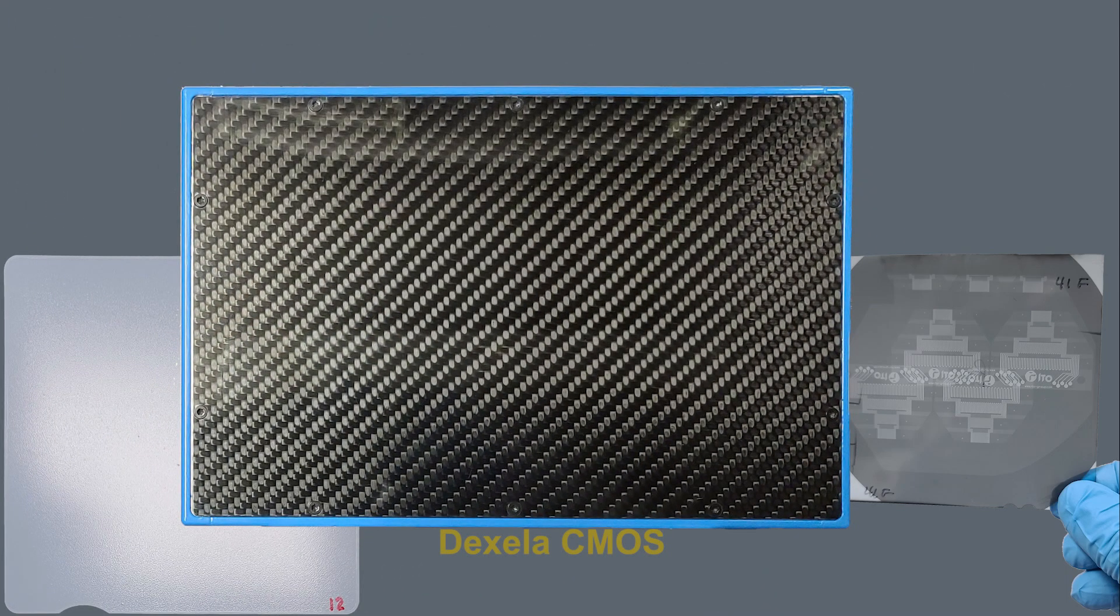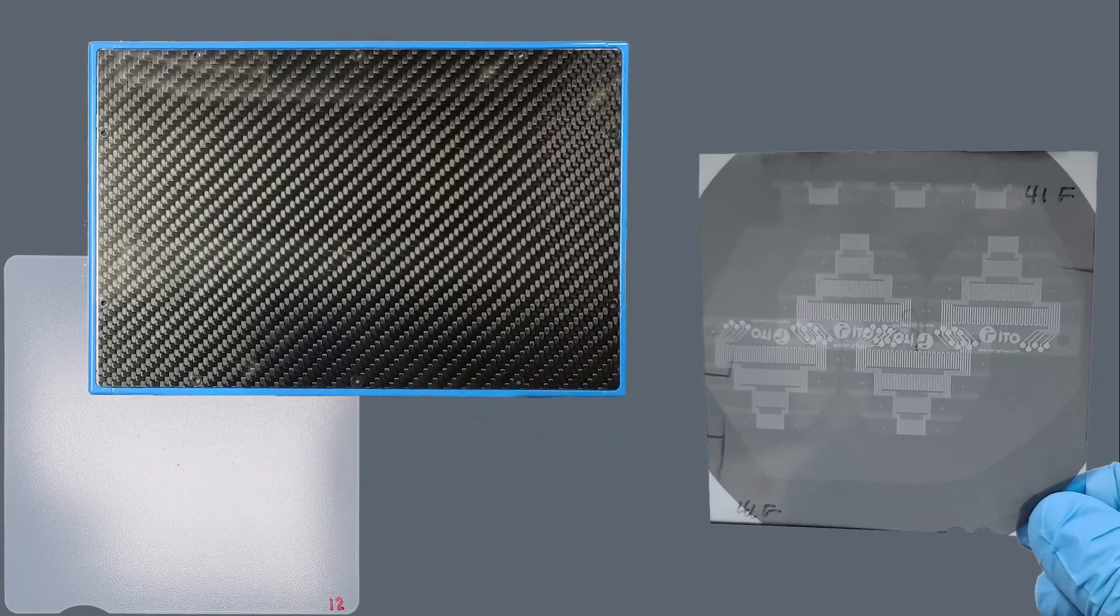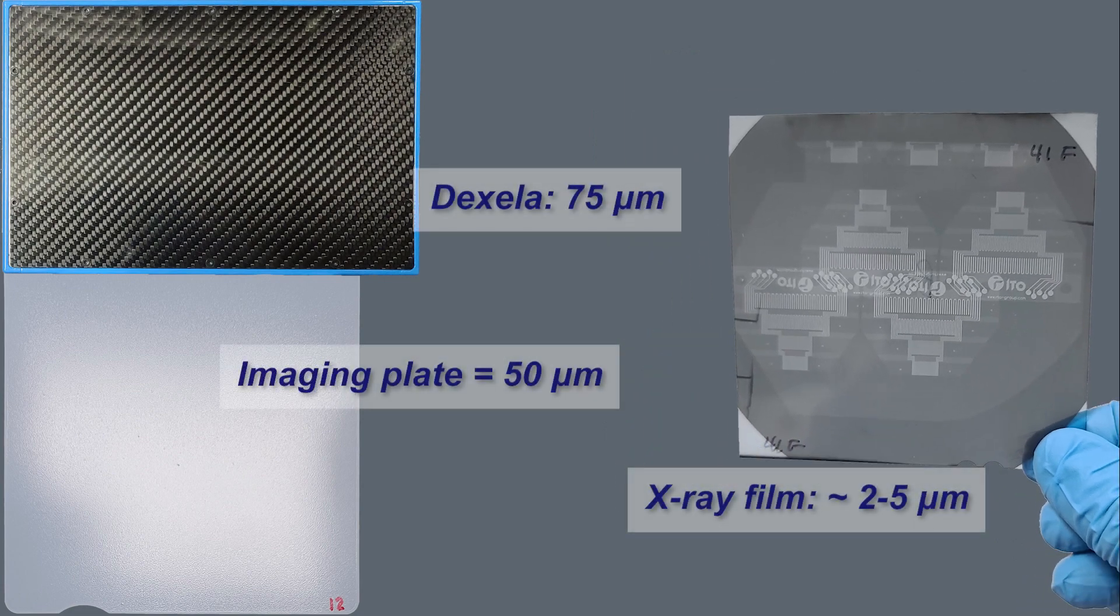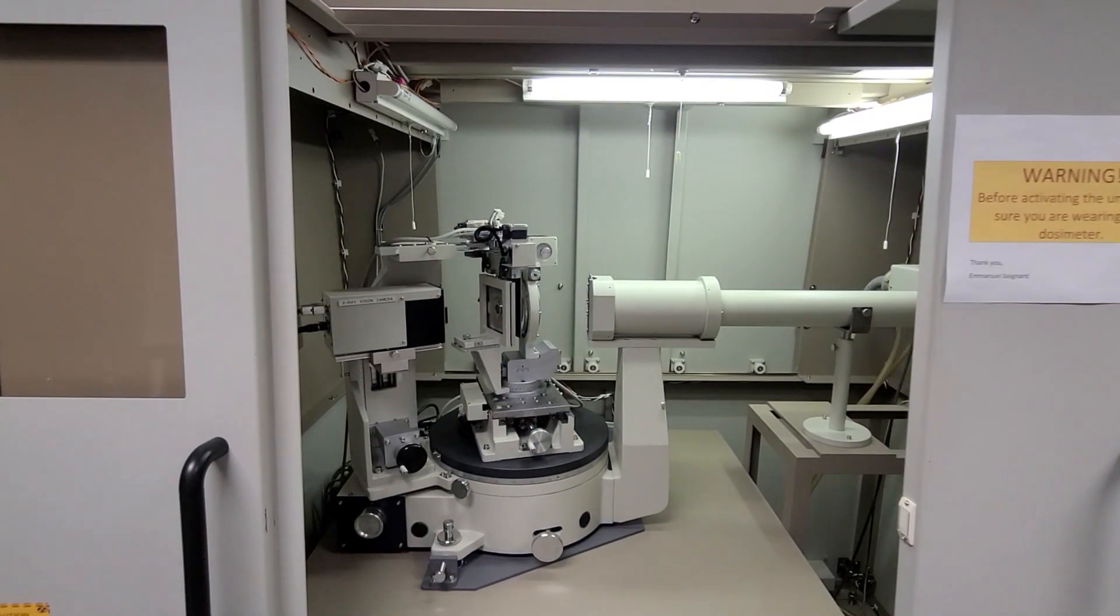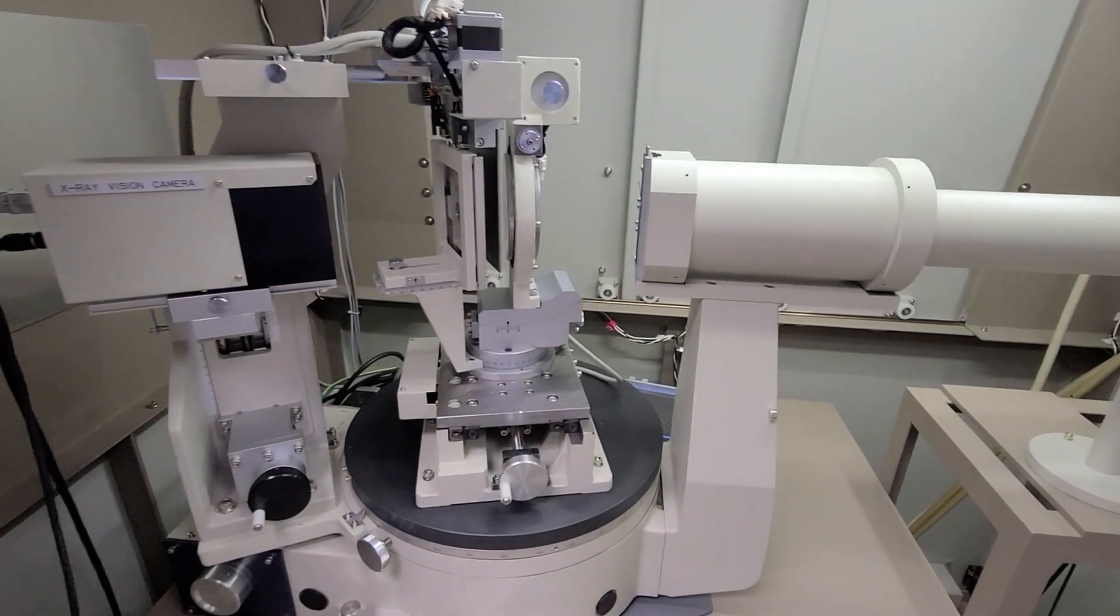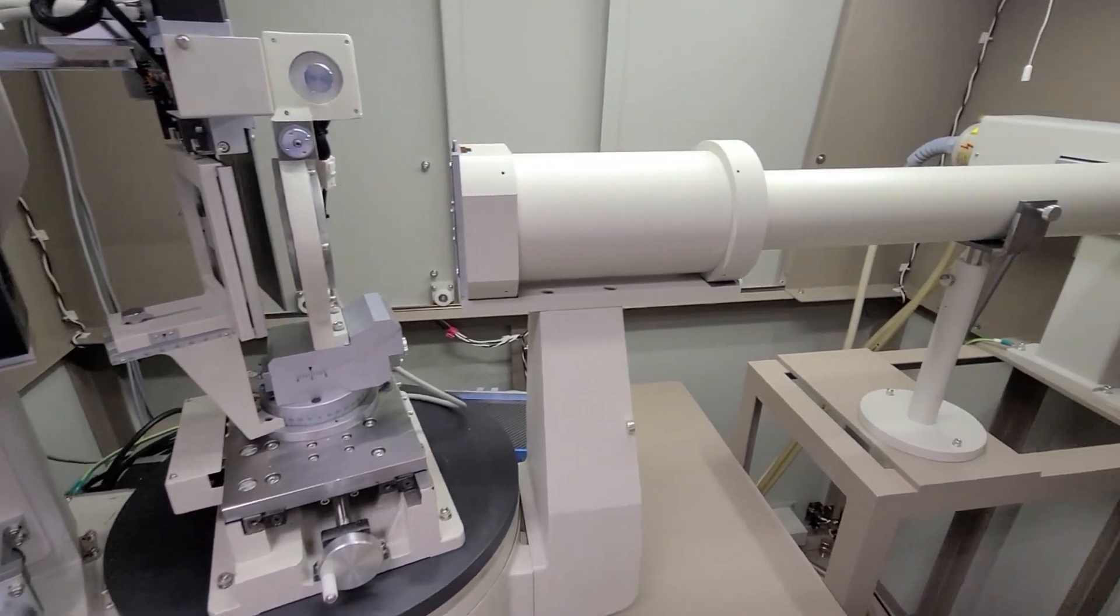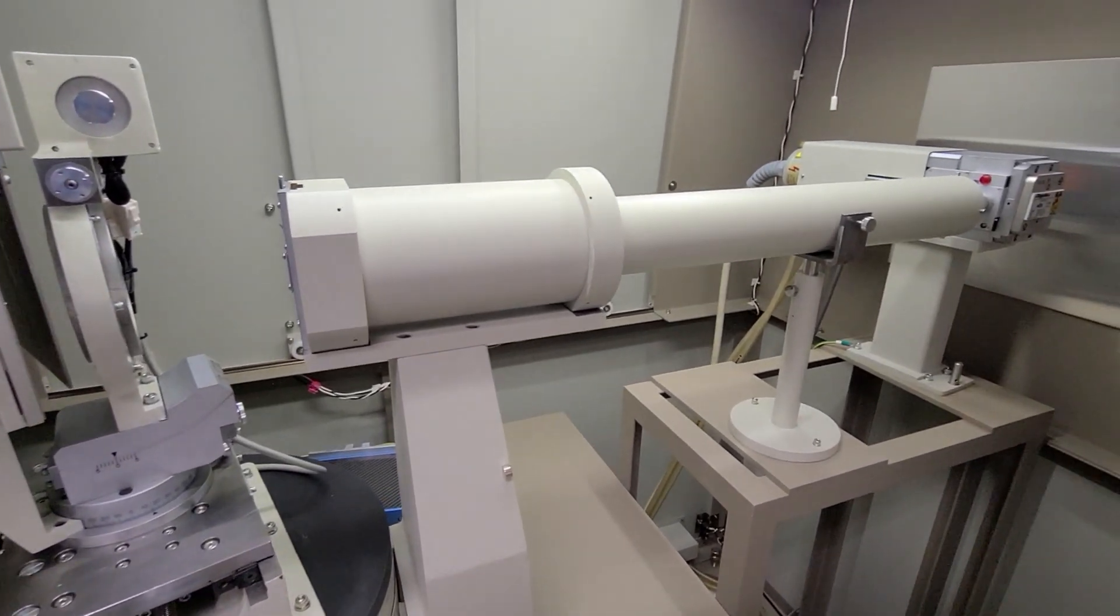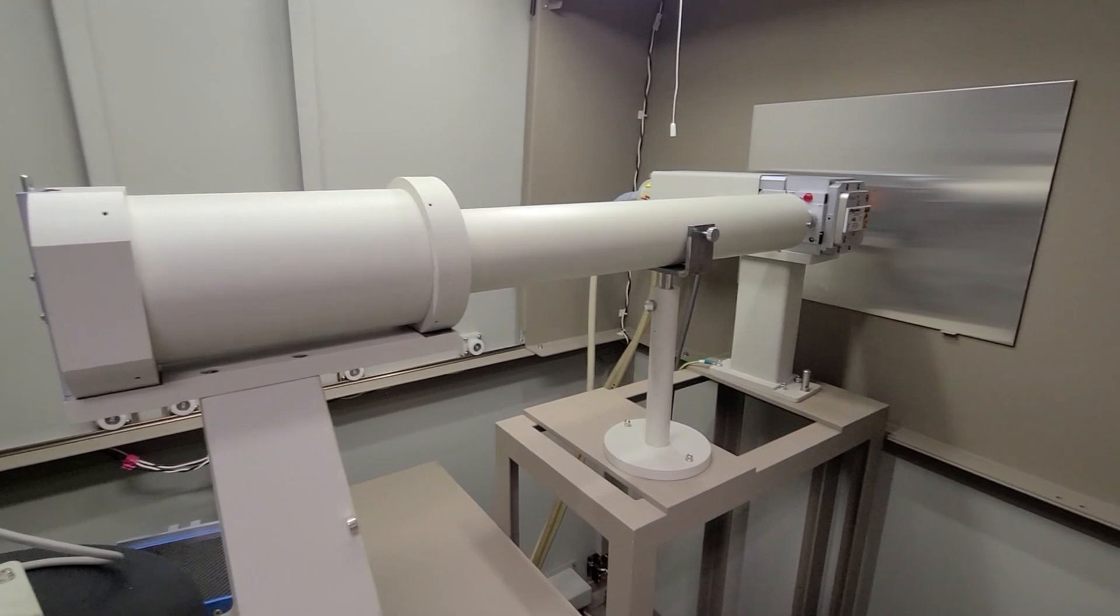Large electronic detectors with small pixel size, and even X-ray films for higher resolution imaging. The pixel size will define the image resolution. Our instrument uses a fixed beam of about 1 by 100 millimeters and scans the sample and detector laterally to cover the full sample area.